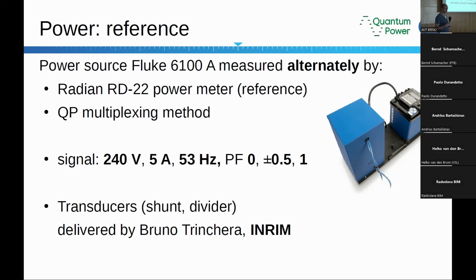The idea of this project is to automatize and simplify digitizer calibration, not to make a new power measurement comparison or anything. So these transducers and this Radian power meter are traveling between my institute and the Norway institute, and then it will go to INRIM again. And we will just do a comparison with the same transducers to be sure that our errors are not caused by the transducers, but only by the method. So we will all be measuring with the same transducers.